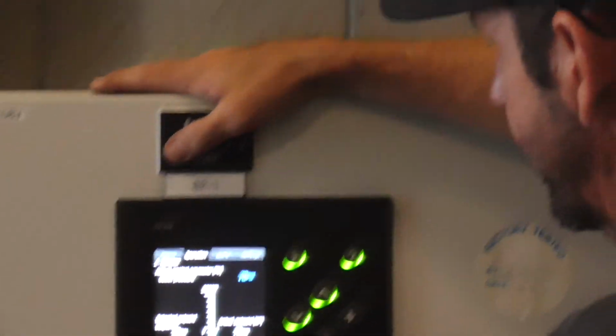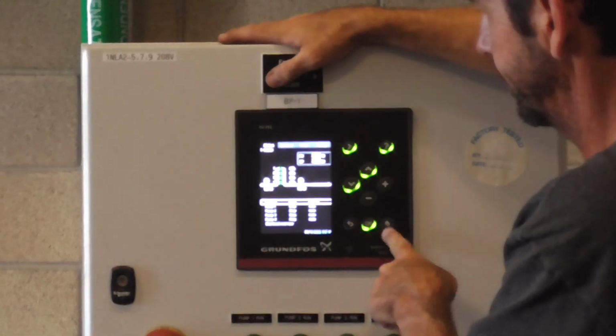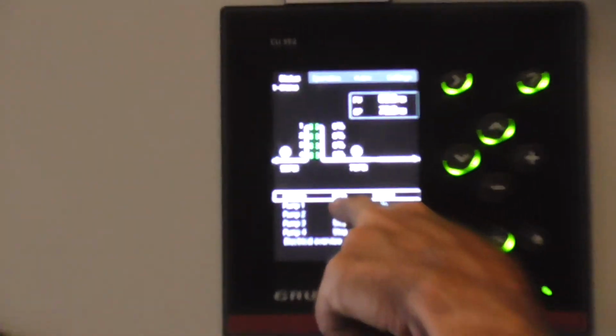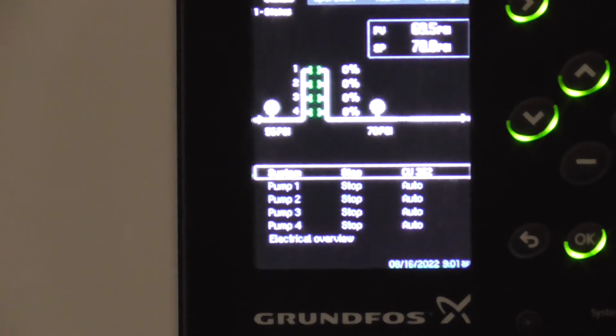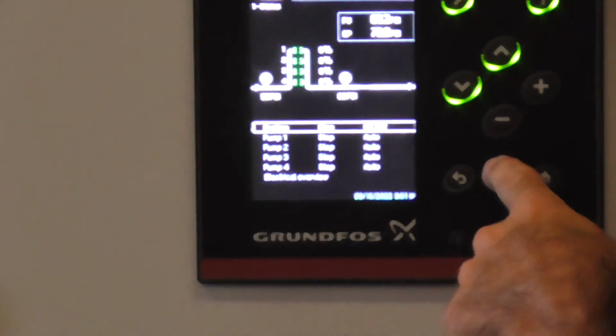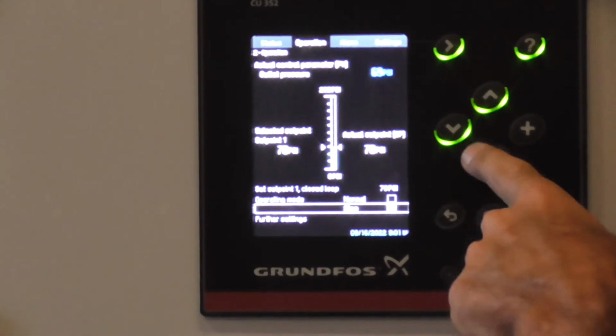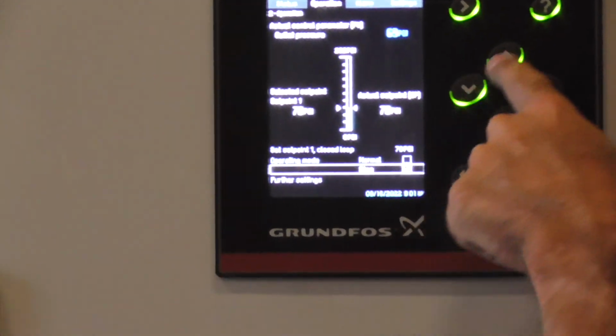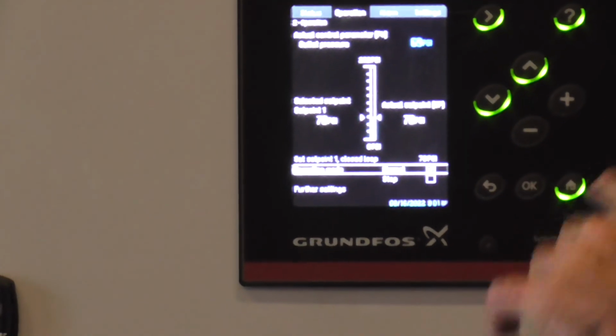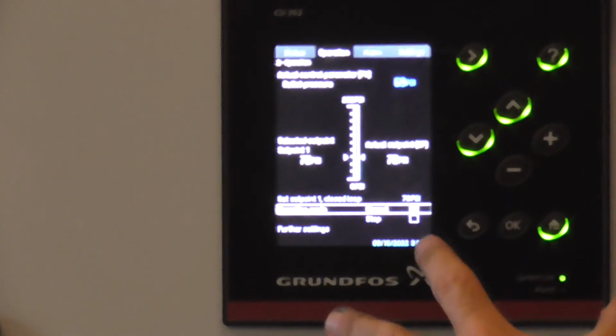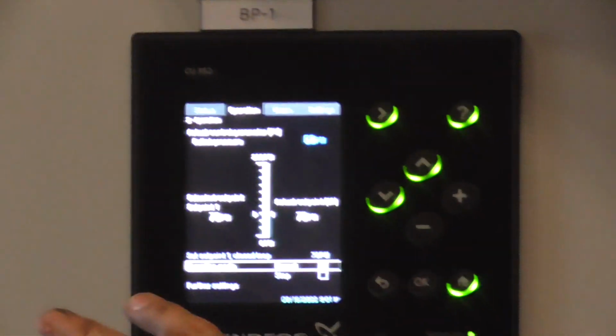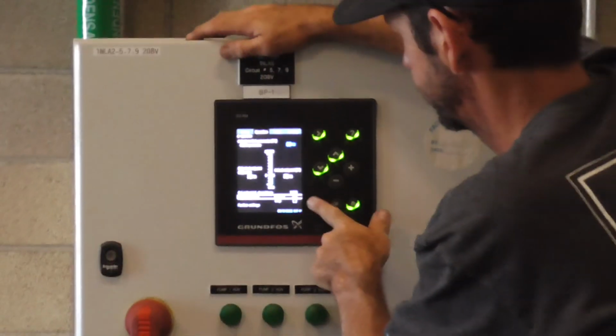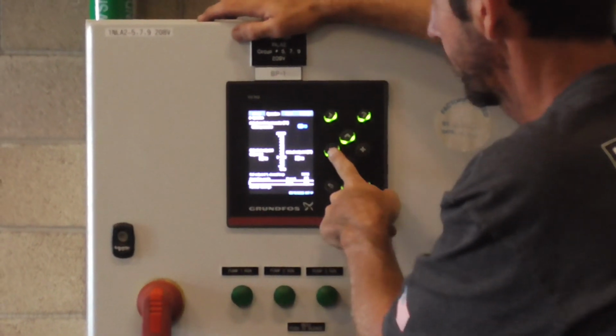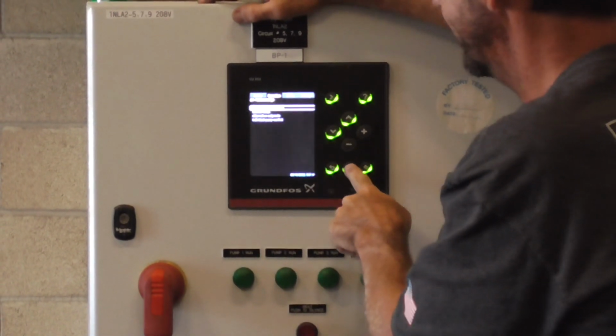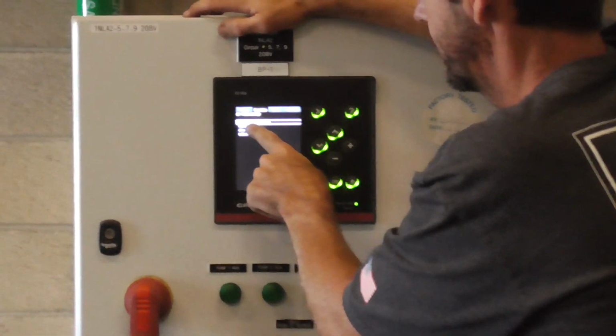Now if we go back to our main display, we can press home. Now we see our system is in stop mode. So now the unit will not work. We're not controlling the pressure anymore. Go back over. We're going to toggle the white bar back up to normal. Now the system itself is back in normal, controlling all pumps to set point. Go down to further settings.